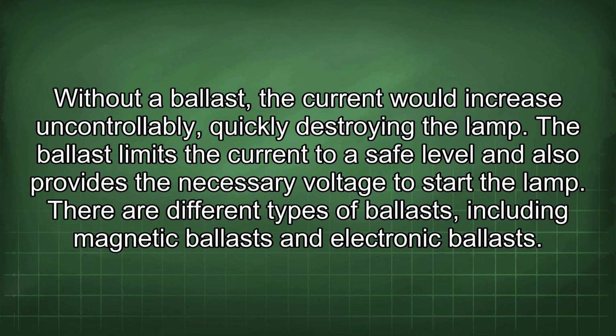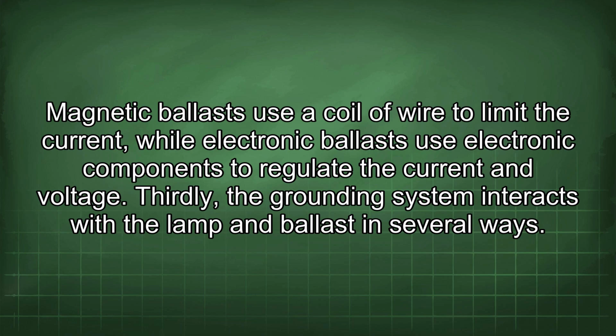The ballast limits the current to a safe level and also provides the necessary voltage to start the lamp. There are different types of ballasts, including magnetic ballasts and electronic ballasts. Magnetic ballasts use a coil of wire to limit the current, while electronic ballasts use electronic components to regulate the current and voltage. Thirdly, the grounding system interacts with the lamp and ballast in several ways.